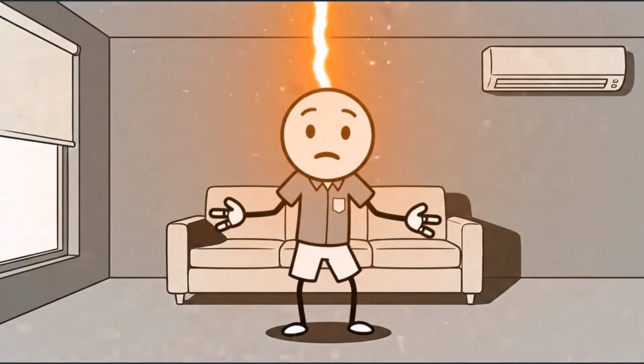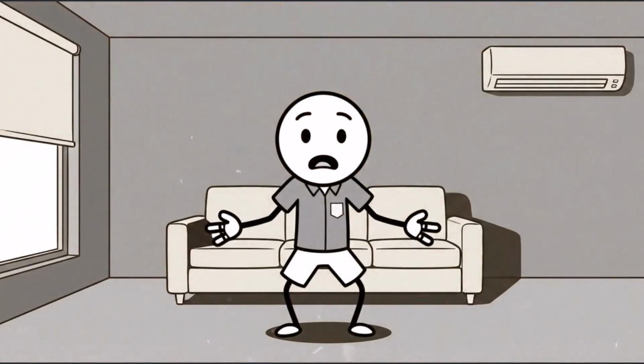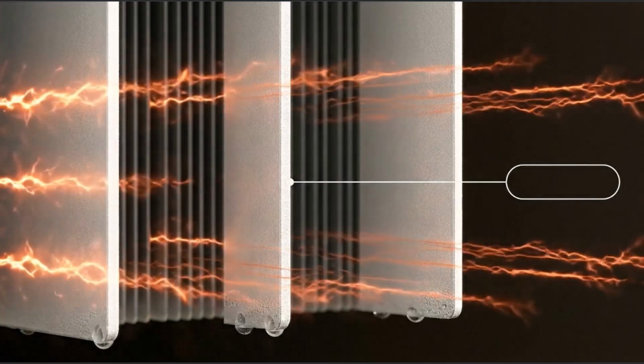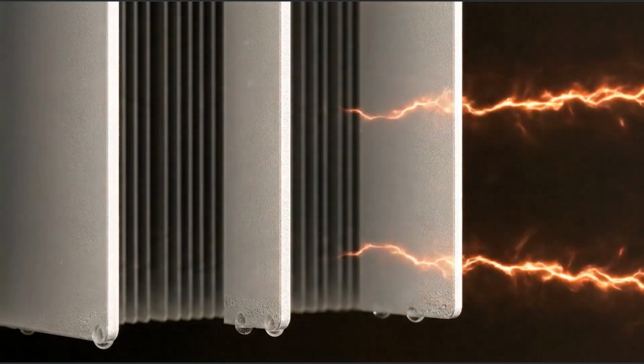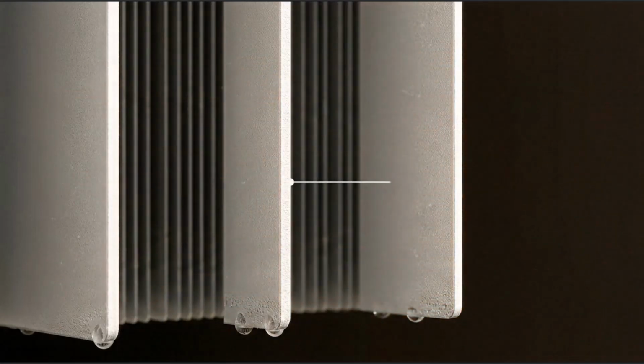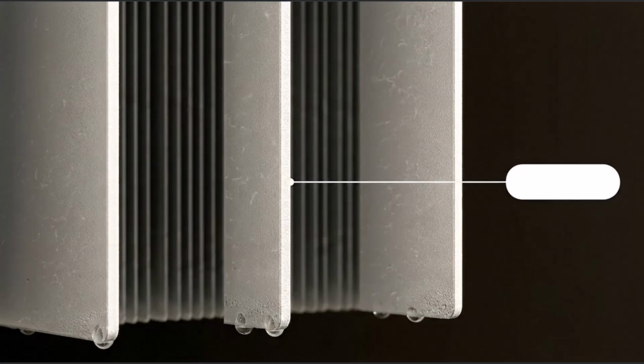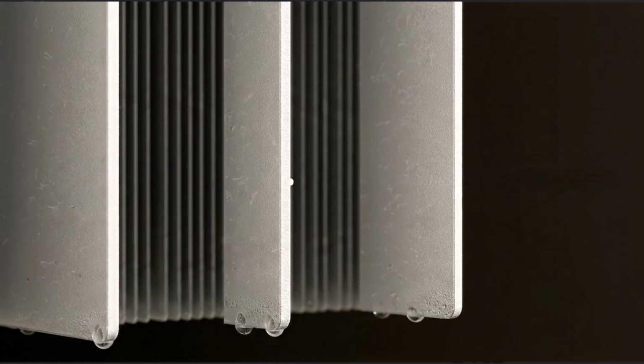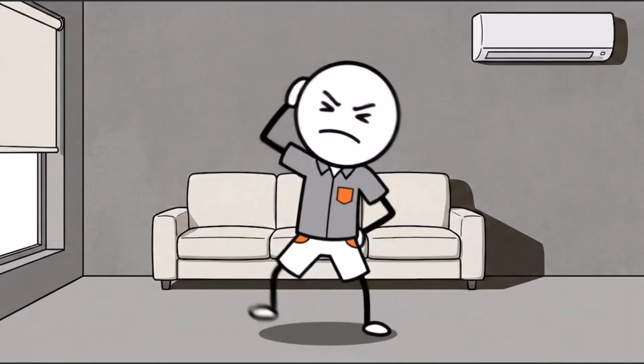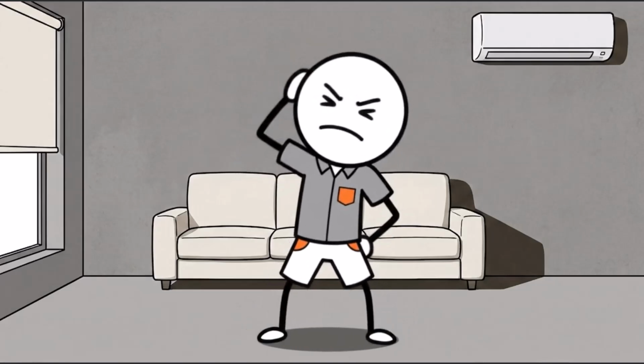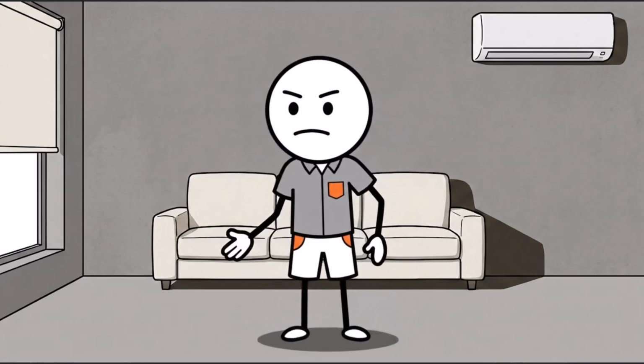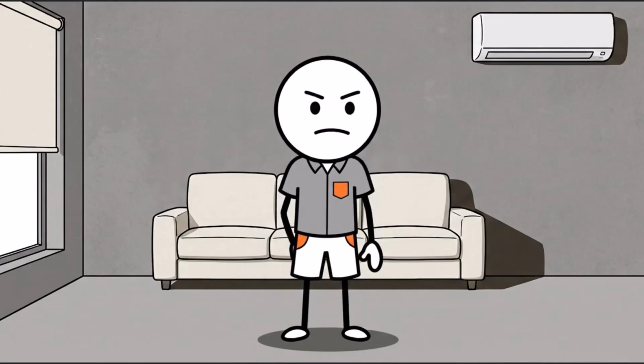When it runs slower, the machine actually gets more efficient. Engineers call that partial load efficiency. In plain English, when the coil is handling less heat, it can dump more heat per watt. I did not believe it the first time I heard it. A machine that runs all day brings a smaller bill. Come on, how does that even work?